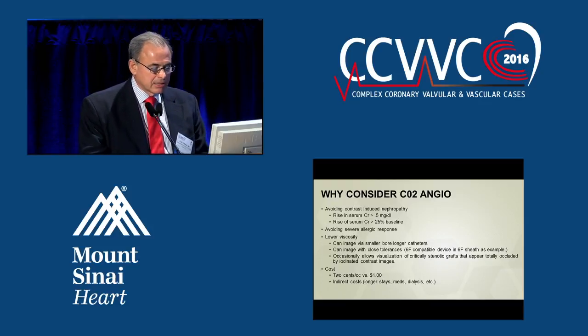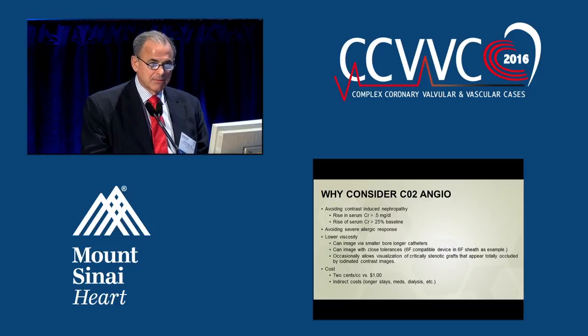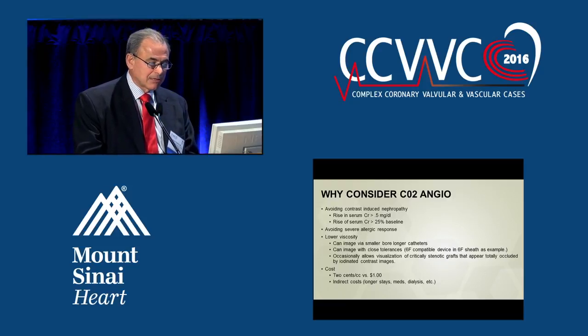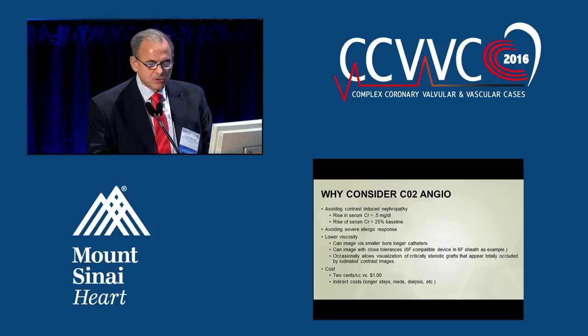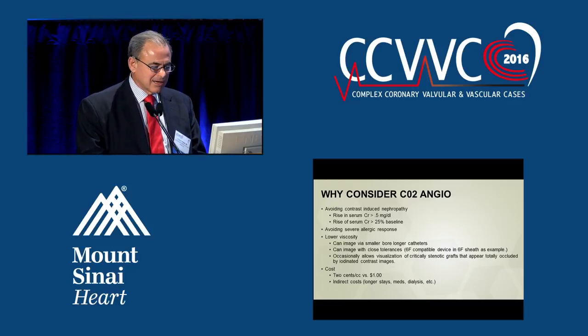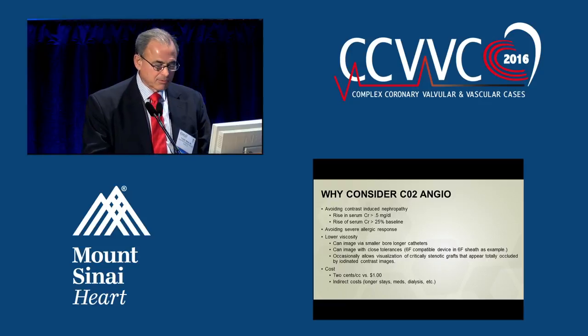CO2 is a lower viscosity agent. Therefore, we can image via very small bore, very long catheters. You can image when you have very close tolerances — six-French devices and six-French sheaths, for instance. And it occasionally allows visualization of critically stenotic grafts that appear totally occluded by iodinated contrast. And finally, it's cheaper.